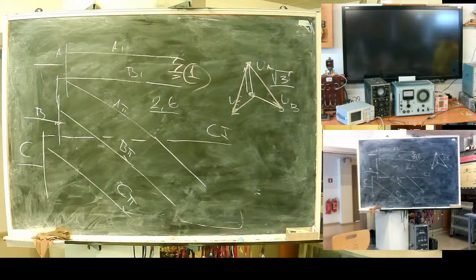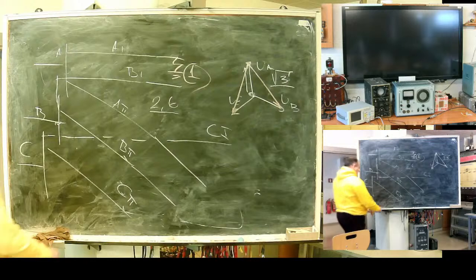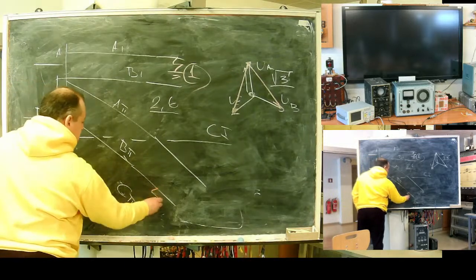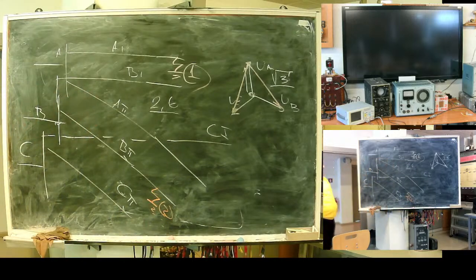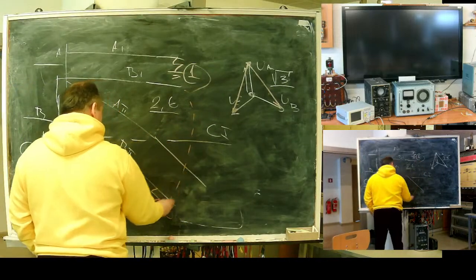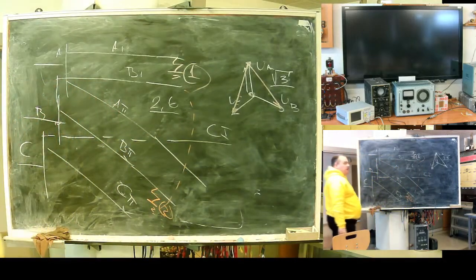And what may happen? In your network somewhere insulation fails and you get a second fault, for example here. It's a problem of earth fault in urban networks. What do we see here? In reality, it's an AB line-to-line fault with quite huge current, 6, 7, 8,000 amps, maybe more.